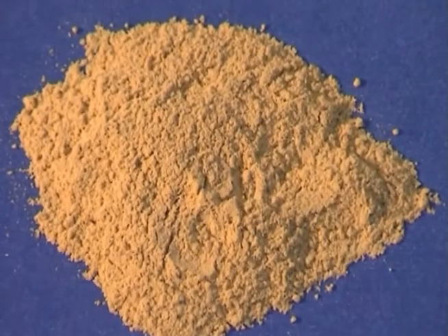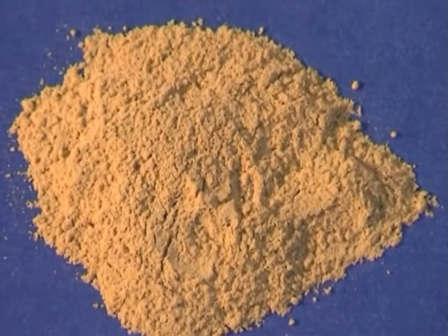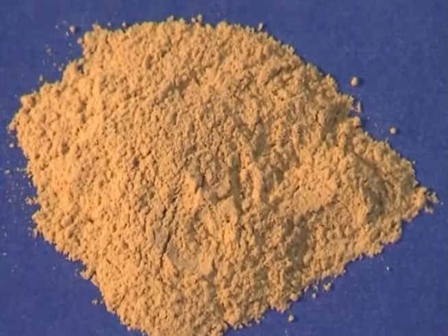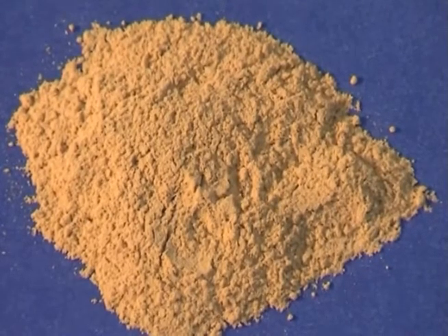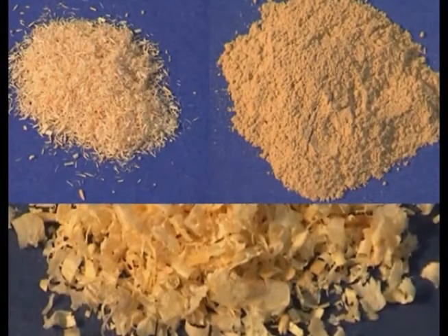This fine dust with a particle size of approximately 0.1 mm is very explosive. The fall speed is less than 20 to 40 cm per second. Dust in real-life wood processing creates a mix of these dust types; the raw materials and the tooling vary depending on the parts produced. The system shall be based on the dust type with the largest risk — in this case, the fine dust.